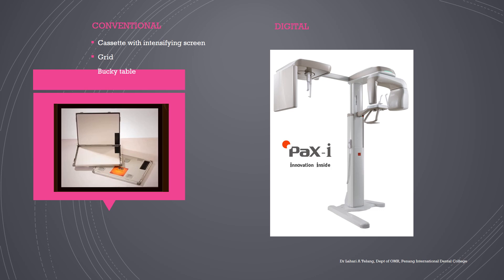This is the panoramic section or the CBCT section, and this section is the cephalometric section. There are guide planes or beams which help to stabilize the patient, including the forehead rest and the external auditory meatus, so that the patient can be stable within the machine while x-rays are emitted from the same x-ray source. The image receptor is the sensor located within the x-ray machine itself. Conventionally, in older days, there were cassettes in which you placed a film with intensifying screens and grids. But now, almost all radiology setups have a digital imaging section in which cephalometric or extraoral radiography can be easily done.